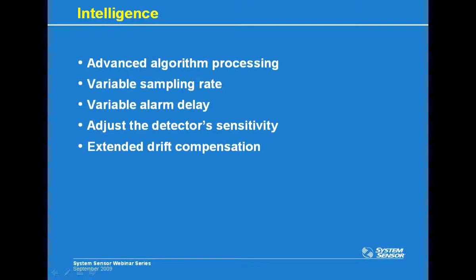Your traditional photoelectric detection technology is not going to respond until it reaches its threshold, that 3 or 4% per foot of smoke. However, with the advanced multi-criteria detector, if it starts to see, let's say, 1% per foot of smoke, but it's also seeing a corresponding rate of rise of heat, or it's seeing a buildup of carbon monoxide that matches what's been programmed and modeled as a real fire characteristic and situation, it's not going to wait until it reaches that 3% threshold. It will actually automatically change its sensitivity to respond much faster.